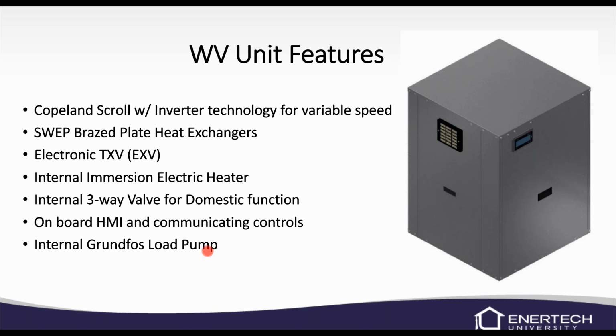It does have an internal immersion electric heater, which is a 9 kilowatt heater. And you can turn that off. It will have a separate power supply. You can also go into the controls and turn it off that way. So if you don't want to use it or you don't want it coming on, you can shut it off. And then you can have it where it just comes on in emergency or when you turn it back on.